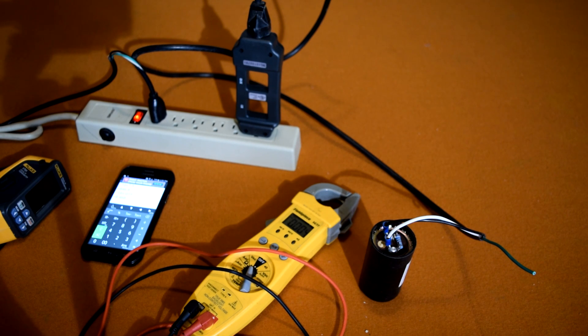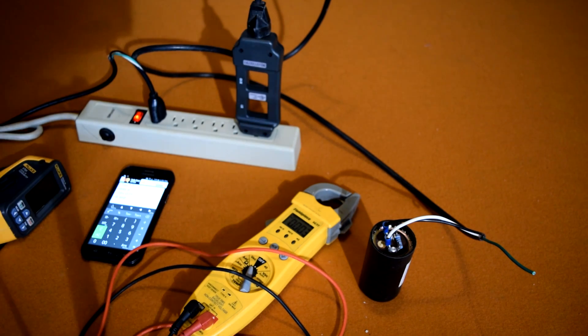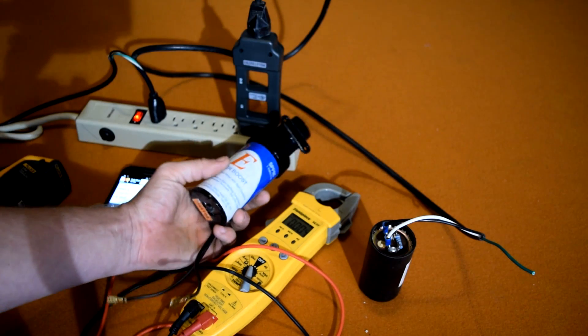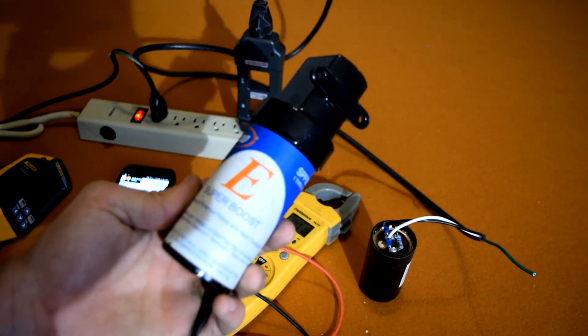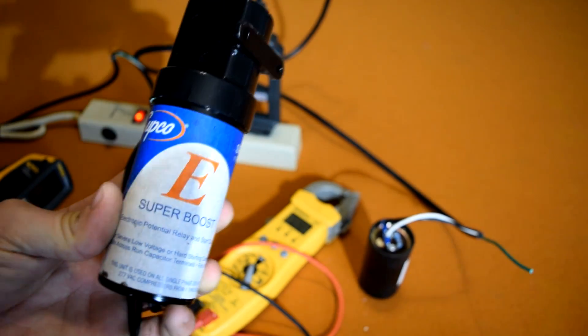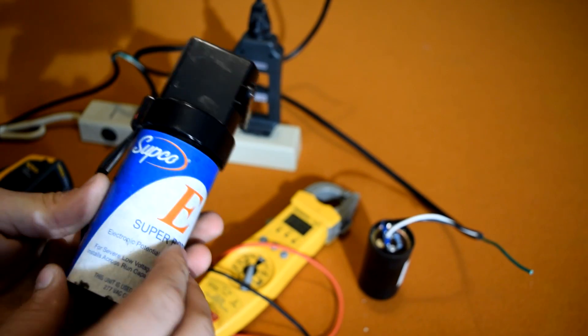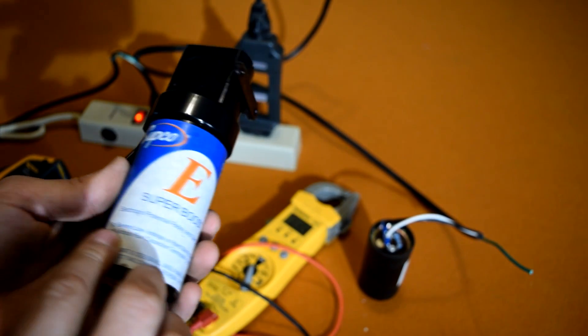Is this something I would put in my house? No. There's something else that you could use called a hard start capacitor. If you're having trouble starting your compressor, there's a device called a hard start. I'll go get one for a heat pump and show you. This here is a Supco brand Super Boost hard start capacitor, which is a very reliable brand.